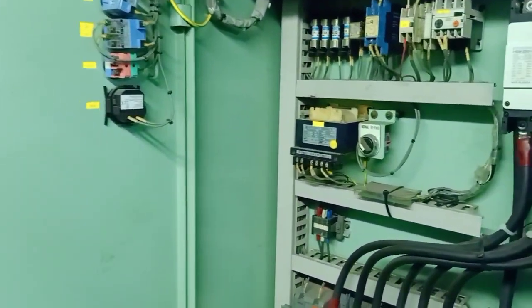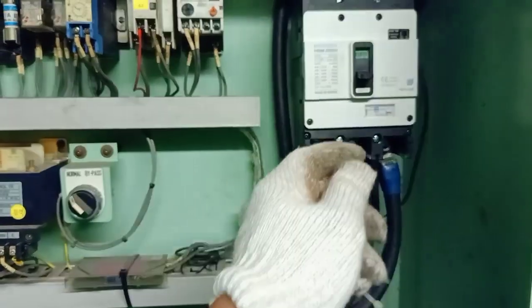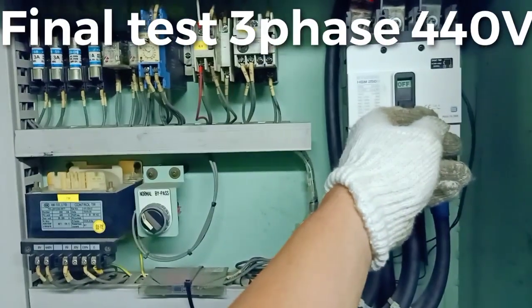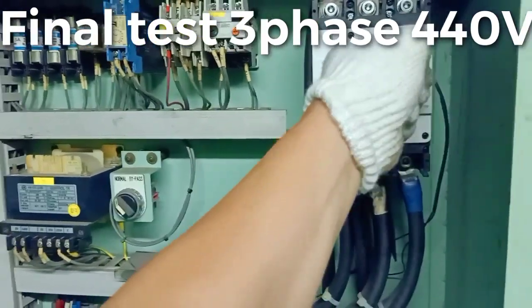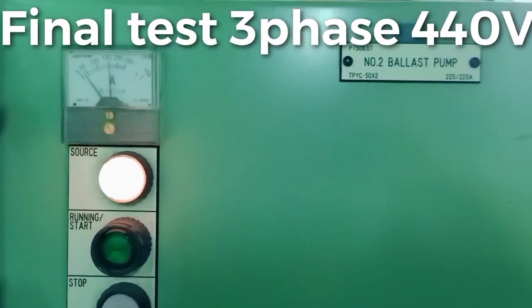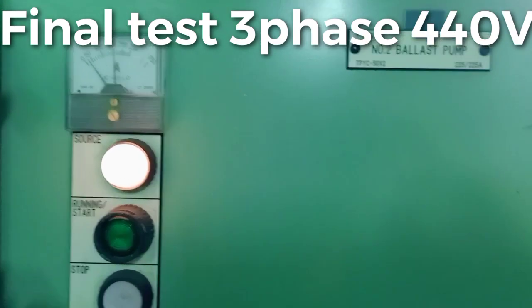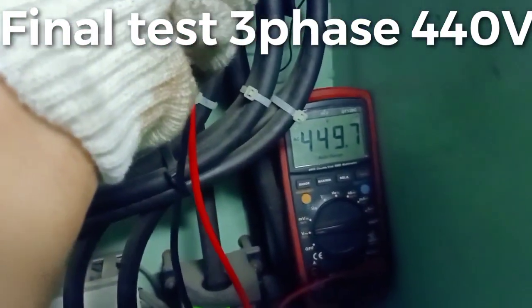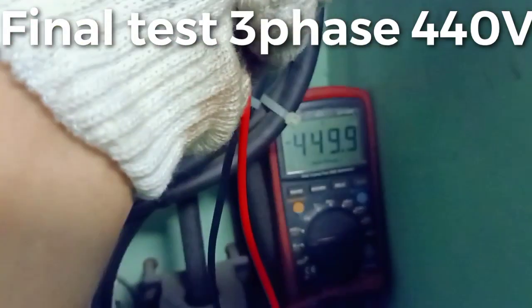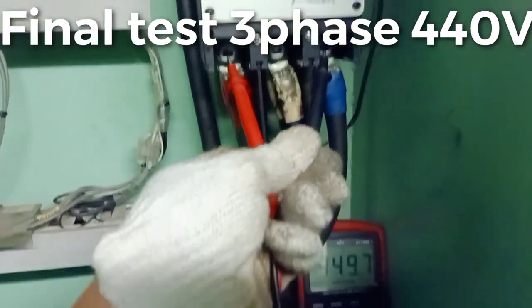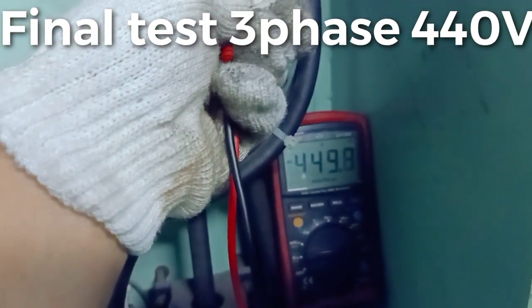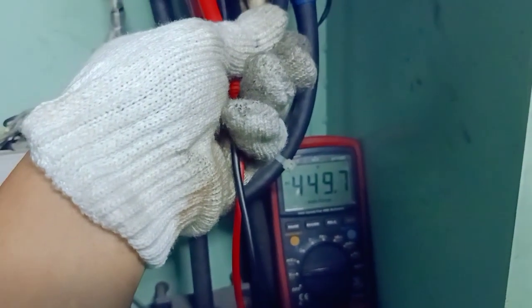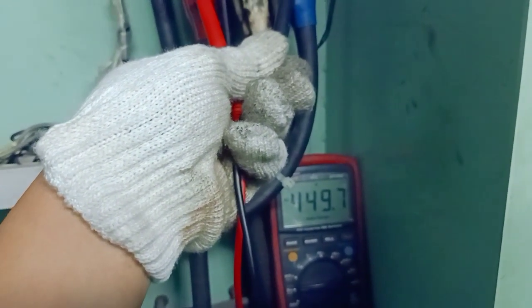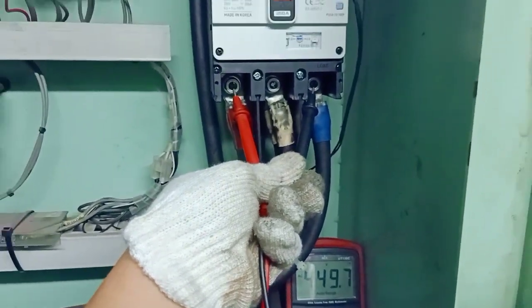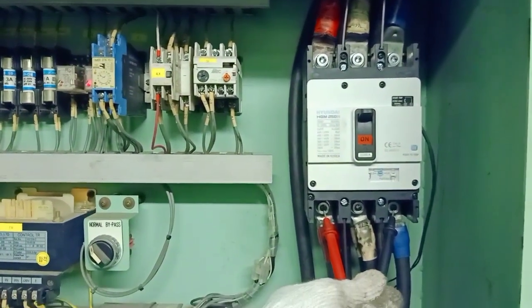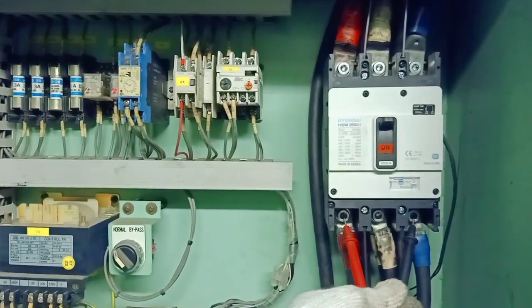Now I'm going to do the final test of this circuit breaker from this ballast number 2 panel board. Now it looks normal. Final check. Working. Next. Working. Last one. So now all working. Line 1, line 2, line 3 have a voltage of 440 volts. So this ballast number 2 panel board is ready in operation.